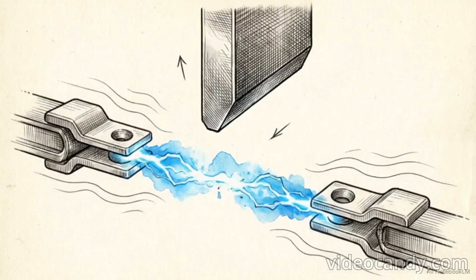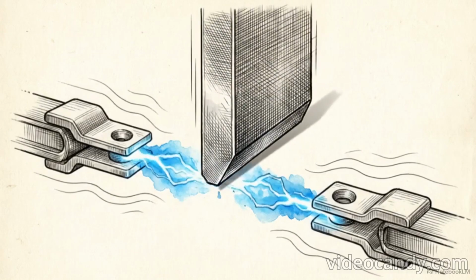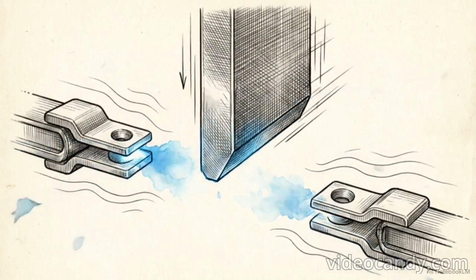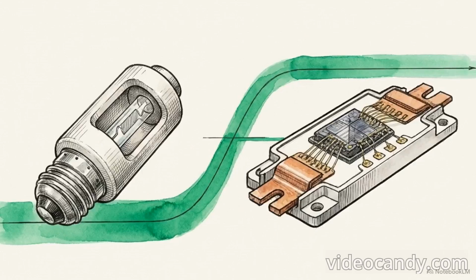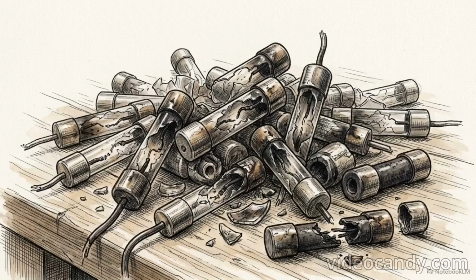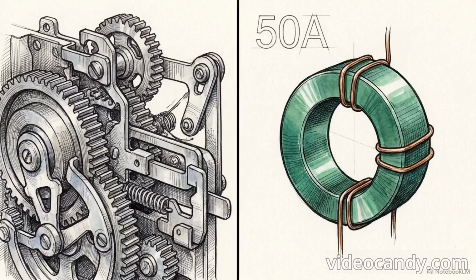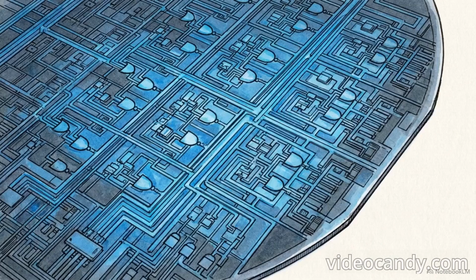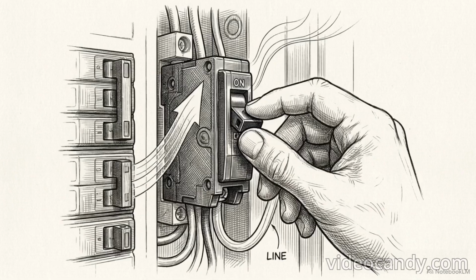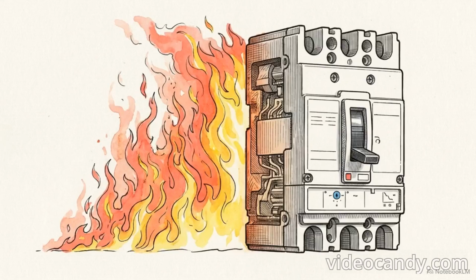Containing these threats requires us to isolate the damaged circuit faster than the physics of the fault can destroy the surrounding infrastructure. Doing that has required a complete evolution in how we build protective hardware. We have had to move from basic sacrificial materials to dual-stage electromechanical latches, precision mathematical differential monitoring, and finally to completely solid-state logic gates. The difference between a localized trip that you reset in your hallway and a catastrophic electrical fire comes down entirely to the microsecond reaction times of these exact hardware architectures.